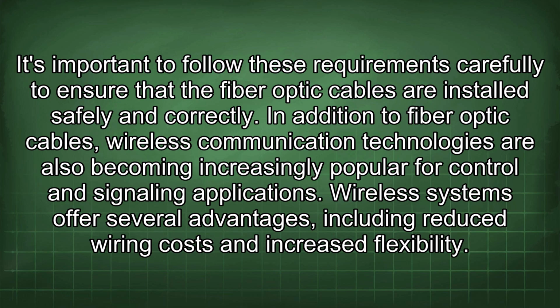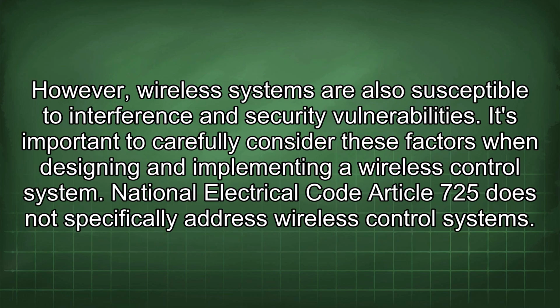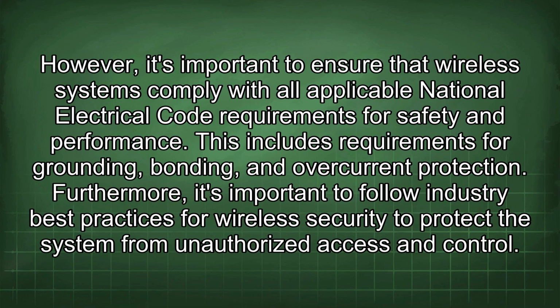In addition to fiber optic cables, wireless communication technologies are also becoming increasingly popular for control and signaling applications. Wireless systems offer several advantages, including reduced wiring costs and increased flexibility. However, wireless systems are also susceptible to interference and security vulnerabilities. It's important to carefully consider these factors when designing and implementing a wireless control system. National Electrical Code Article 725 does not specifically address wireless control systems. However, it's important to ensure that wireless systems comply with all applicable National Electrical Code requirements for safety and performance. This includes requirements for grounding, bonding, and overcurrent protection. Furthermore, it's important to follow industry best practices for wireless security to protect the system from unauthorized access and control.